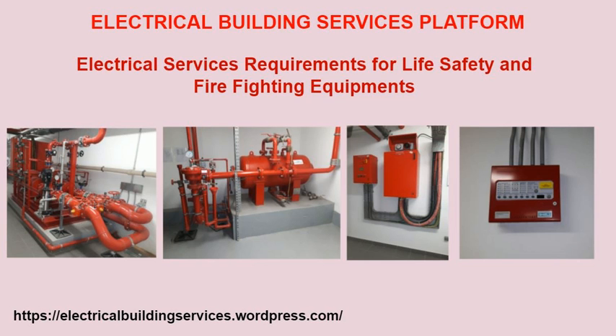Number 16, where the secondary electrical supply is to be taken from a separate substation to that supplying the primary electrical supply, the electrical supply to the two independent substations should be taken from two separate high voltage supply and not originate from the same substation. The failure of one substation should not lead to the failure of the other. The two independent substations should be adequately separated.